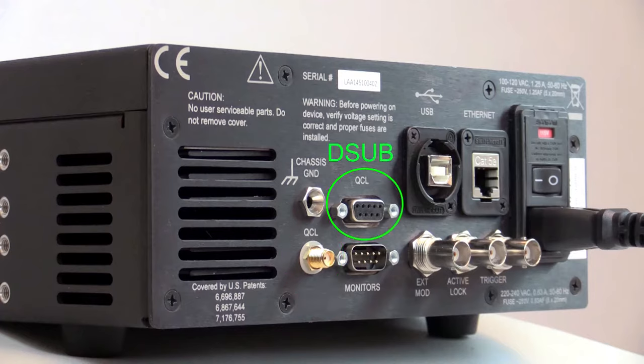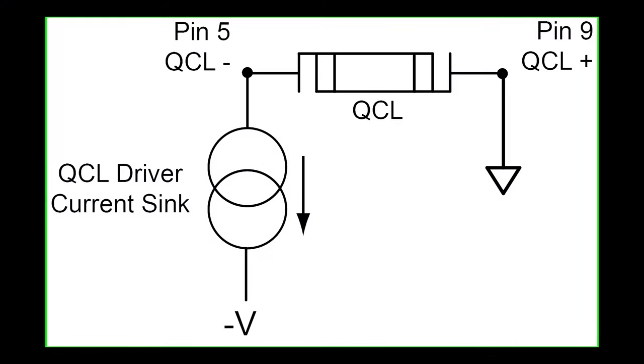The QCL instrument operates as a negative voltage supply current sink. Load current sources from the system ground through the QCL load where it is regulated by the negatively biased controller. With the traditional laser, this is commonly called grounded anode operation.